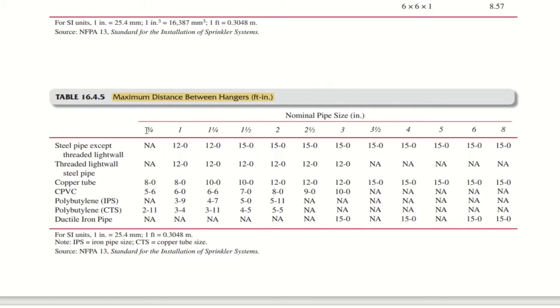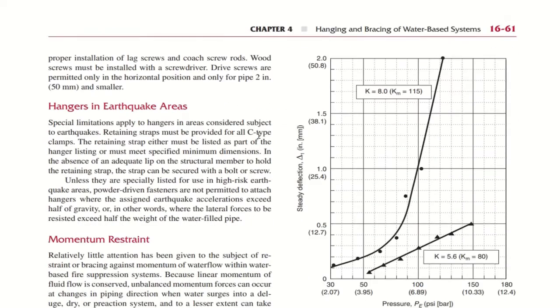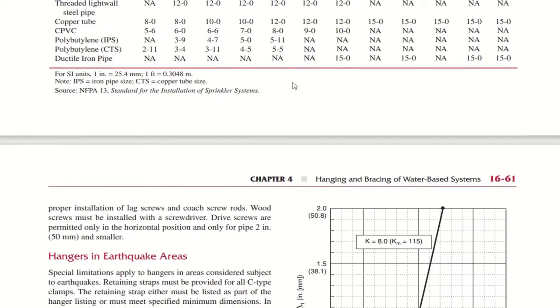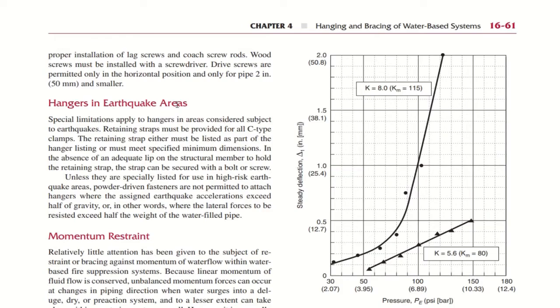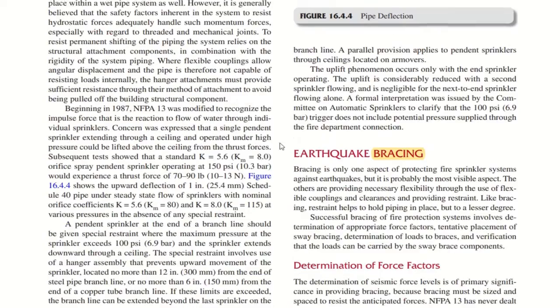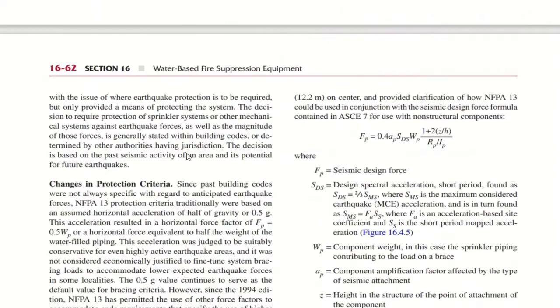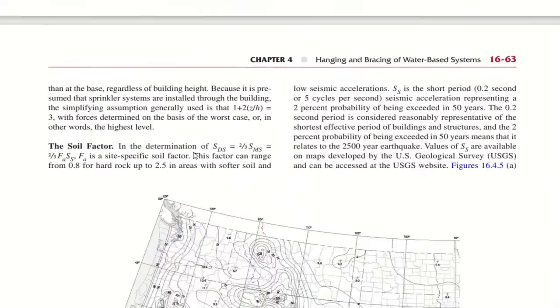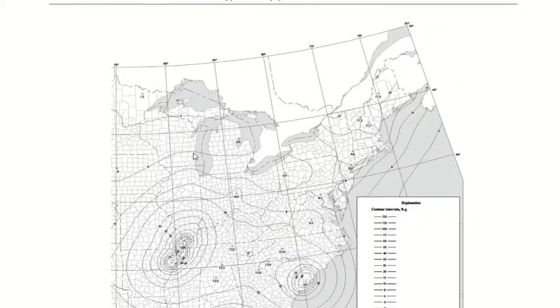So here you can see the pipe sizes from 3/4 inch till 8 inch. On the left hand side you have the pipe. For example, if you are considering steel pipe, then the distance between the hangers can be 15 feet for 3 inch pipe. Okay, so you can go through this now. Apart from that, hangers in earthquake areas and so many things are there. It's like an ocean. You just go through these things.